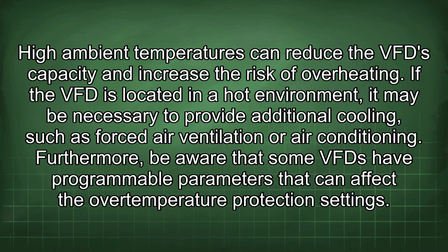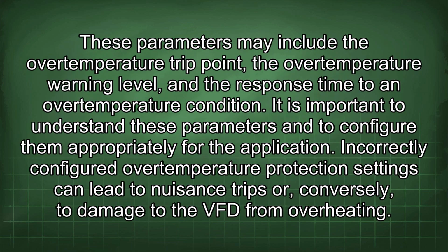Furthermore, be aware that some VFDs have programmable parameters that can affect the overtemperature protection settings. These parameters may include the overtemperature trip point, the overtemperature warning level, and the response time to an overtemperature condition. It is important to understand these parameters and to configure them appropriately for the application. Incorrectly configured overtemperature protection settings can lead to nuisance trips or, conversely, to damage to the VFD from overheating.